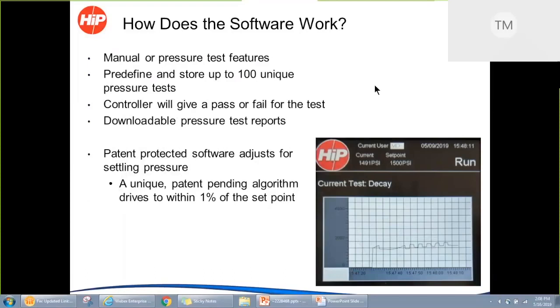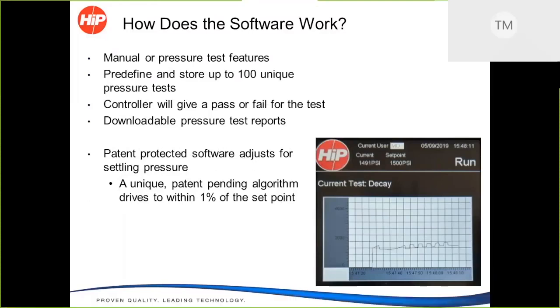You can basically set up a test in the machine. For example, say you want to do a pressure decay test at 10,000 psi. You can tell the unit to drive up to 10,000 psi, how long you want to hold it for, how you want to measure your test. When that test is completed, it'll determine if you passed or failed that test. So everything's automated. Think of it, you set up your test, you hit the go button, you can actually walk away while the machine does the work for you and come back and see a pass or fail criteria on that product.